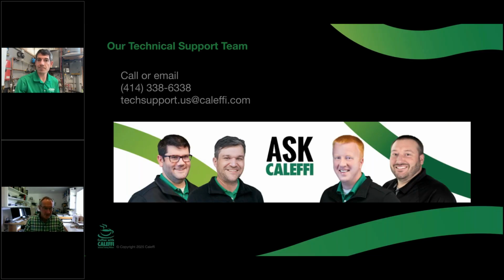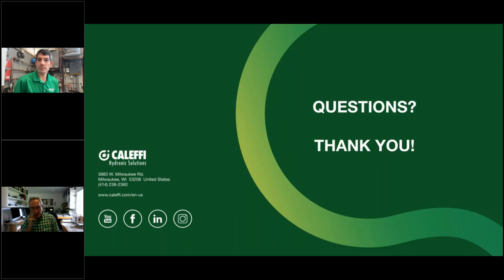So it's probably worth mentioning too that there was a European circulator manufacturer that at one point was creating what we'll call micro circulators. And Hot Rod, I'm sure you remember those. These are tiny little circulators that drew like 2 or 3 watts when they operated. And they were actually setting up for panel radiator systems. And the goal was to displace thermostatic radiator valves with these micro circulators. And the concept was sound. The cost became kind of prohibitive. I don't think it really ever caught on. But it was amazing to see these tiny little circulators that, as they say, literally maybe 3 or 4 watts when they're operating, and each one would operate as a separate zone. And, of course, it had to be wired and so forth.